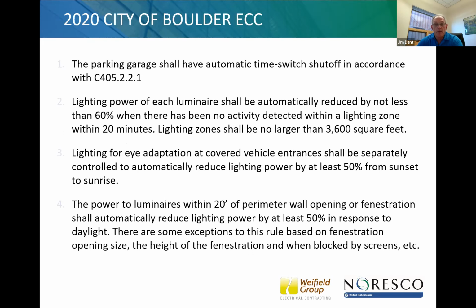Next. So a parking garage has to have an automatic time switch that shuts off 60% when there's no activity. The lighting for eye adaptation at covered vehicle entrances shall be separately controlled to automatically reduce lighting power by at least 50% from sunset to sunrise. So when it's dark, you don't need that eye adaptation.